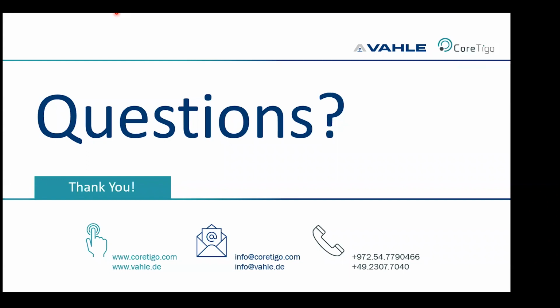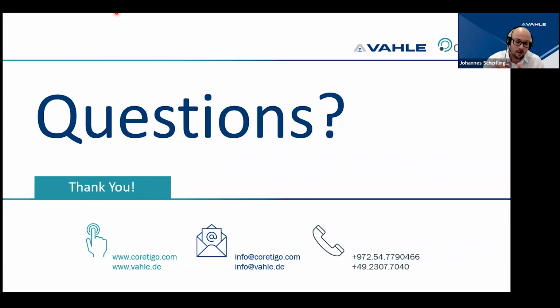Mm-hmm. Okay, thanks. Actually, one more question here. Johannes, regarding the power, what are the limitations of power, assuming 24-volt DC and current accordingly that's available on the shuttle? And are there any other voltages available, for example, 48-volt DC? Yeah, let me answer the first question with 24-volt. The smaller pickup has 70 watts, which is 3 amps, and the bigger one has 150 watts, about 6 amps at 24-volt. Also, if there is a need for 48-volt, it is possible to switch the pickups in series, so that you get, for example, 2 smaller pickups and have 48-volt. That's the possibility. And from the primary side, we have systems up to 30 kilowatts. So that means in one segment, you can have up to 420 pickups. So basically no limits on this.